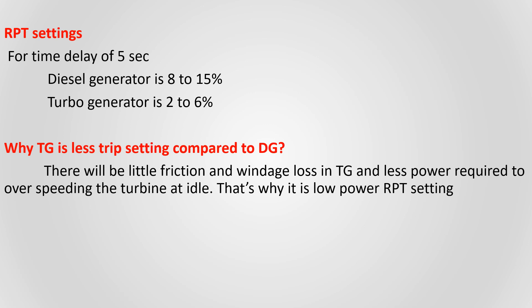Reverse power trip setting for a diesel generator is 8 to 15 percent, and for a turbo generator it is 2 to 6 percent. The setting value can vary and depends on the maker. For example, if the generator is producing 3000 kilowatt and the trip setting is 10 percent, that is 300 kilowatt. But when reverse power flows, the value of the power reading in the controller shows minus 300 kilowatt, because the generator is taking power from the busbar.